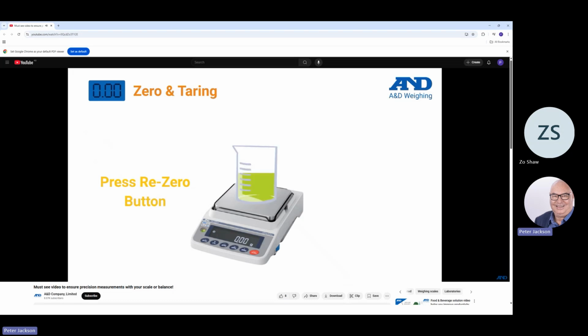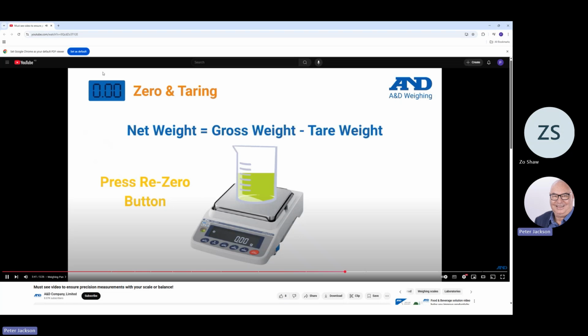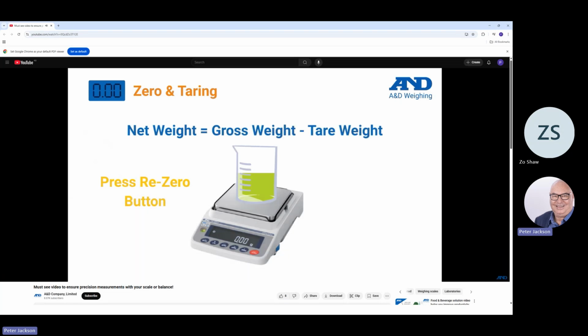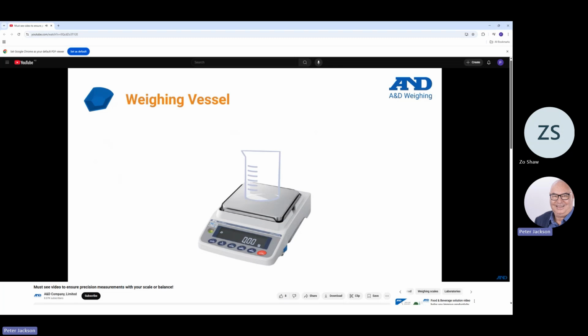in the container. The balance will store the container weight and subtract it from the total gross. This ensures that only the net weight of the sample is measured and the container weight is subtracted. When using tare, please note the maximum capacity of the balance will be reduced by an equal amount of the vessel weight. When weighing inside a container, the smallest possible weighing vessel should be used to maximize the weighing range.